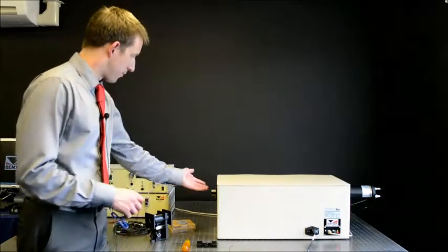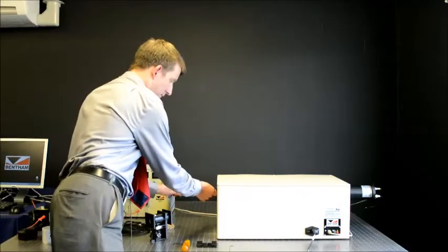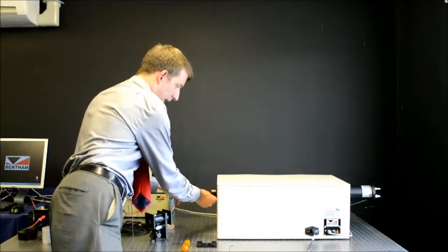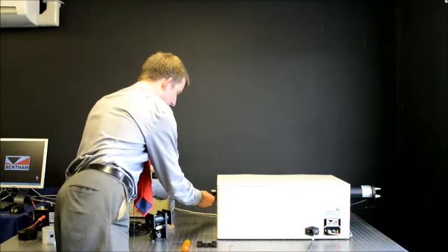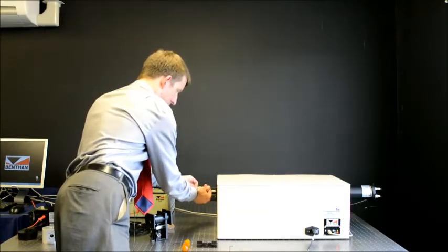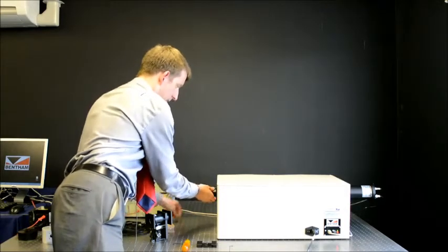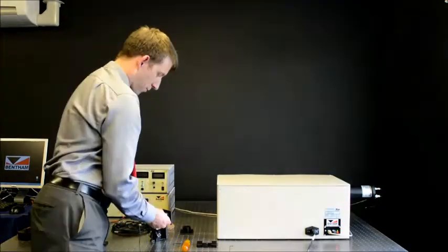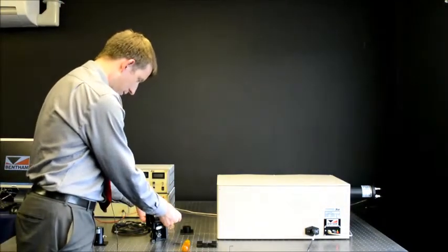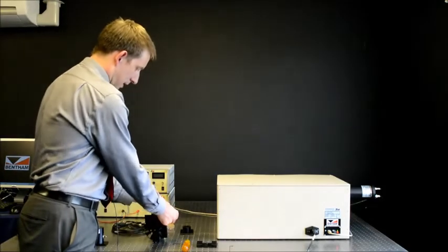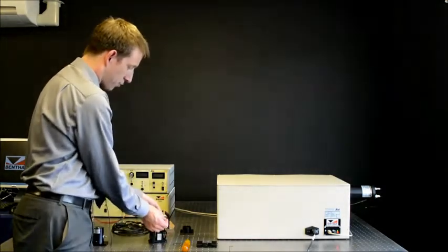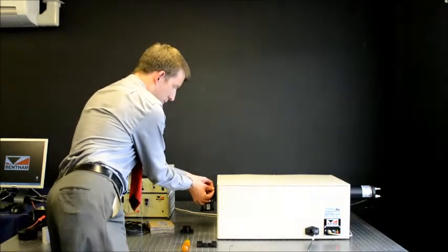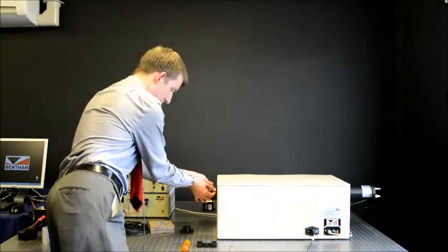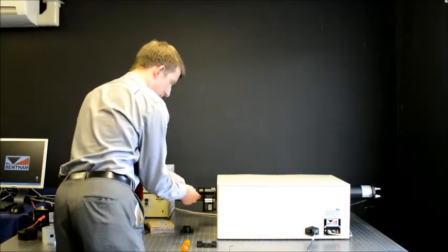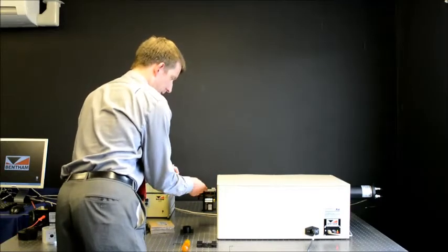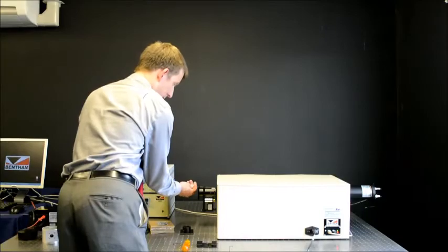We can remove directly the fiber bundle adapter plate from the entrance slit of the monochromator and fit the infrared relay optic to the entrance port. I only use the top 2 screws for ease of access, and the orientation should be such that the optical chopper is closest to the monochromator, so we must make sure that this is the case. And I will attach that firmly, and we have that as input optic.